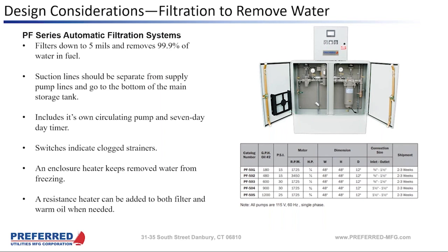In fact, I've had complaints in the past where the person's saying, I'm getting a water alarm on my filter, but there's no water. I had my tank tested and there's no liquid water in the bottom of my tank. And with a coalescing filter, we can actually pull that out of suspension. So we had a situation where there was suspended water in the fuel being removed by our polishing system that they couldn't measure in the tank itself. Well, that just means the polisher was doing its job. Exactly. Not letting water accumulate at the bottom of the tank.